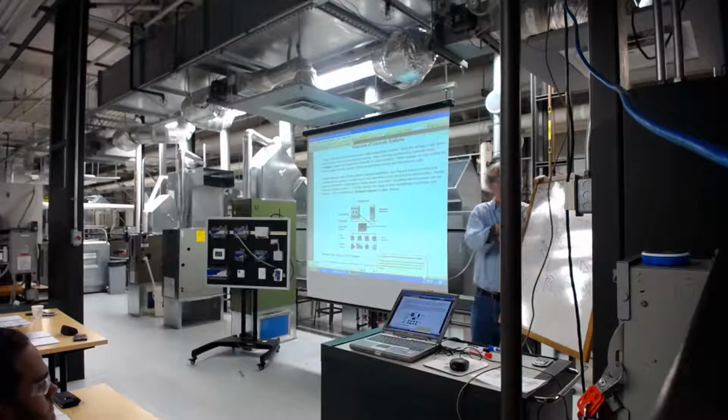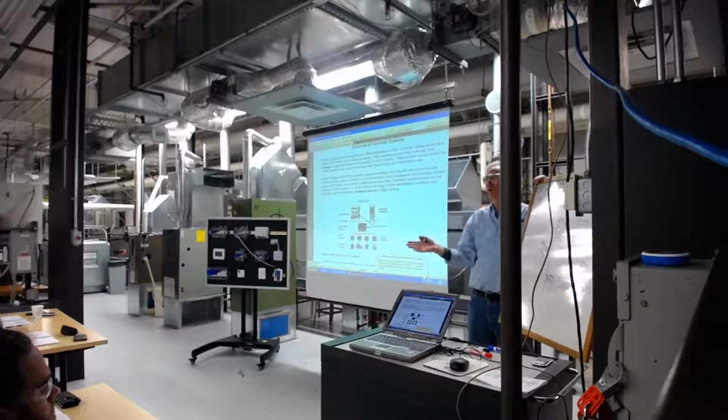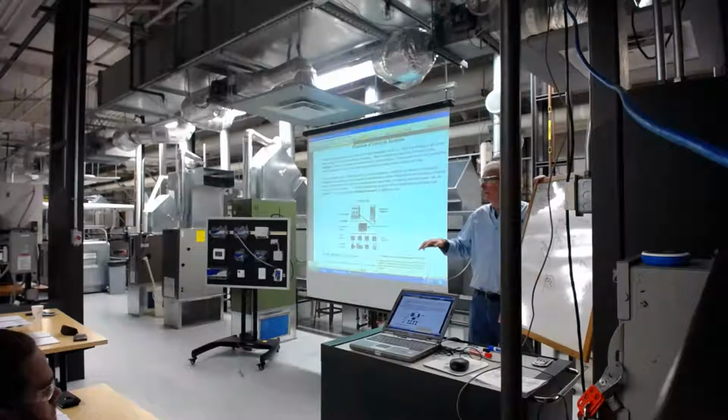Neither one of us can make changes to the database. I cannot delete points in the software; objects cannot be deleted or added. I can't add a feature because that's not what I do, that's not what I should be doing. However, this young lady shows up. She's a building chief. Well, guess what? She's got administrator rights. She can do all the above. So you see how you can set up your passwords for particular people's skills.